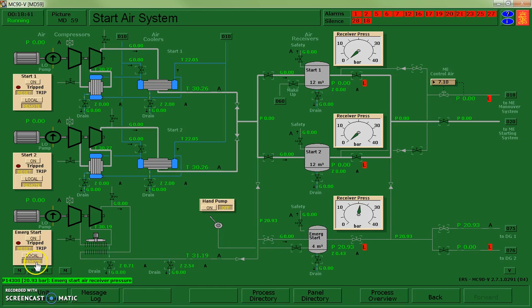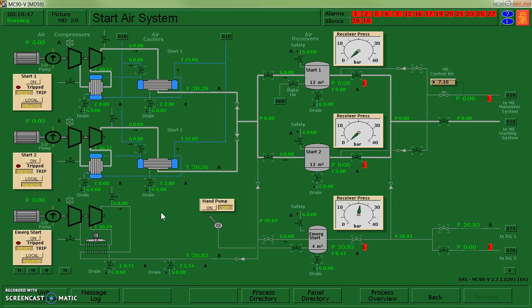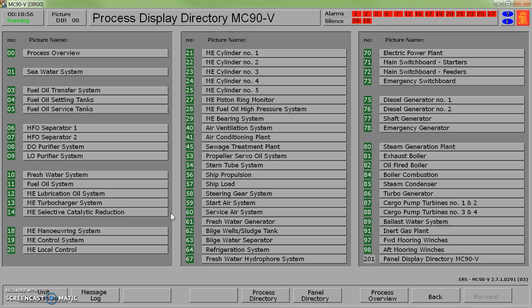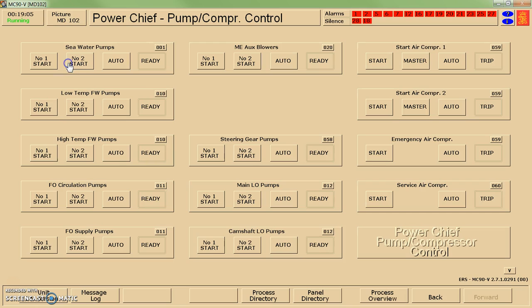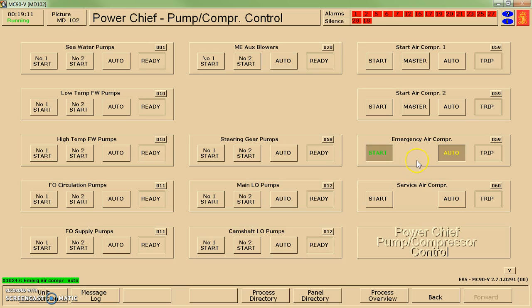I switched it to remote so I'm going to set it over to automatic controls and eventually do the same with the rest of the air compressors. If I go to the home screen and push page down, I can get to page 102, which is the pump compressor control. I'm going to set the emergency air compressor into auto mode and we can see it just triggered to automatically start.